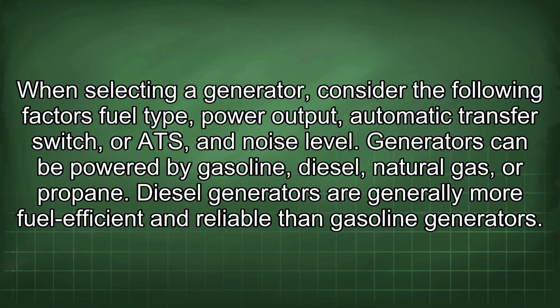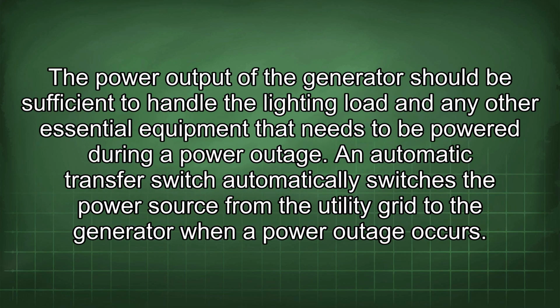When selecting a generator, consider the following factors: fuel type, power output, automatic transfer switch, or ATS, and noise level. Generators can be powered by gasoline, diesel, natural gas, or propane. Diesel generators are generally more fuel efficient and reliable than gasoline generators. The power output of the generator should be sufficient to handle the lighting load and any other essential equipment that needs to be powered during a power outage.